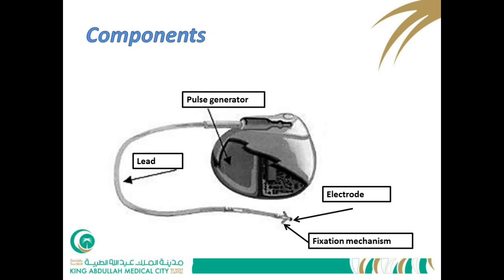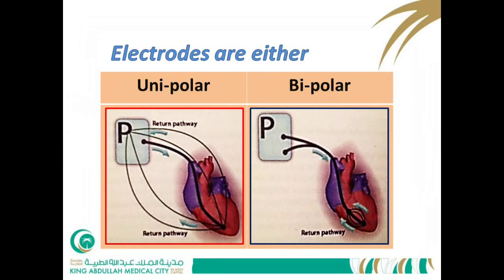The electrode has an extra fixation mechanism that prevents dislodgement from the myocardium. Electrodes are either unipolar or bipolar. In both types, the cathode is inside the myocardium. In a unipolar electrode, the anode is the casing itself. In a bipolar electrode, the anode is a nodule located just proximal in the same axis of the lead — if you see such a nodule on the lead, it is a bipolar electrode.